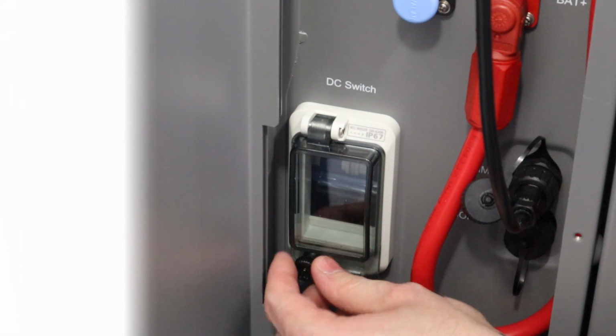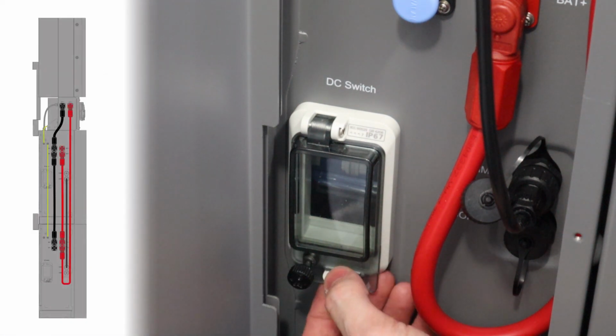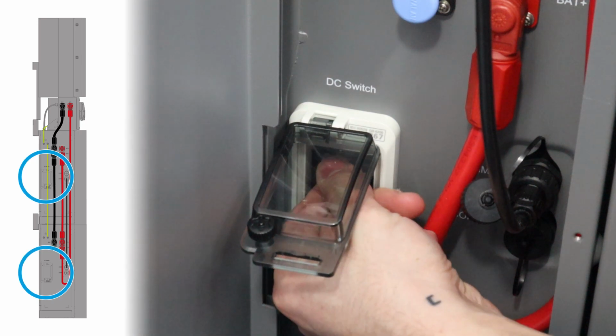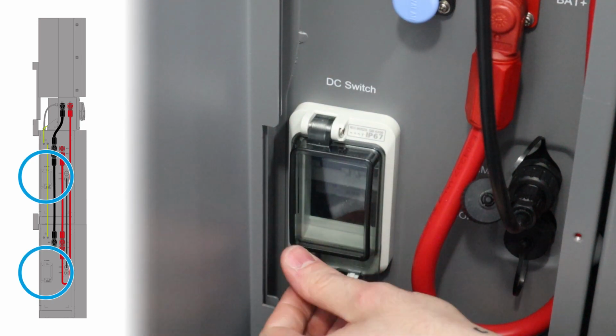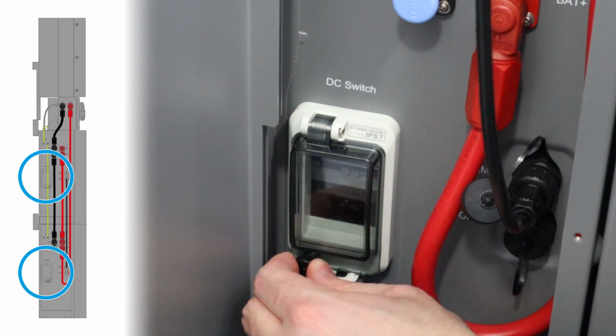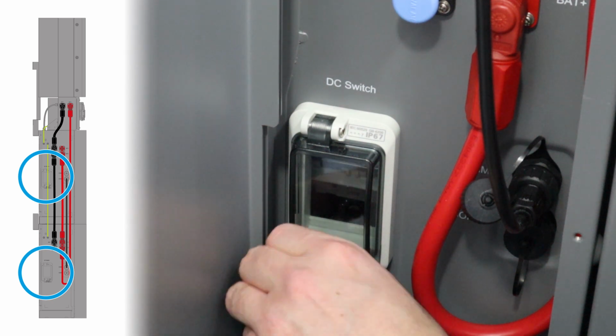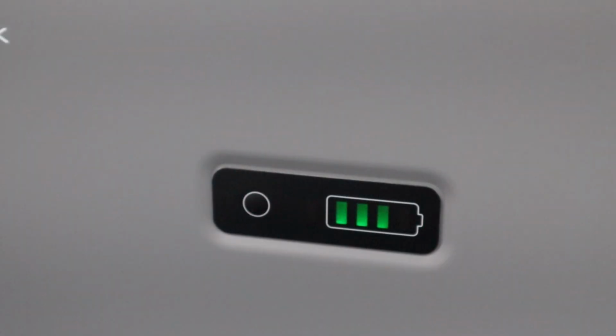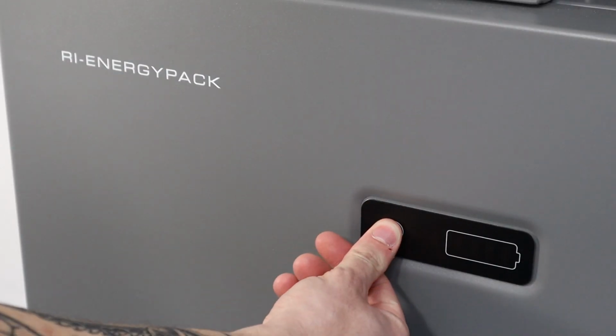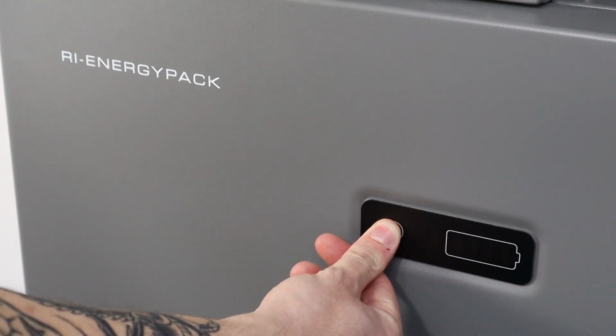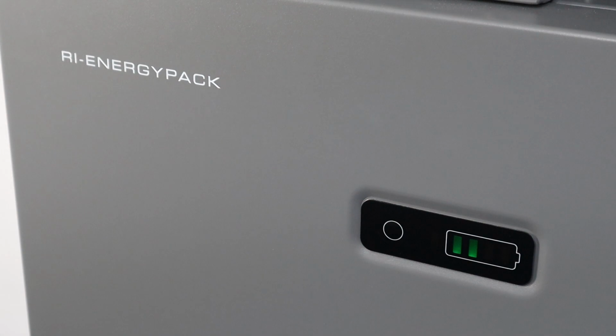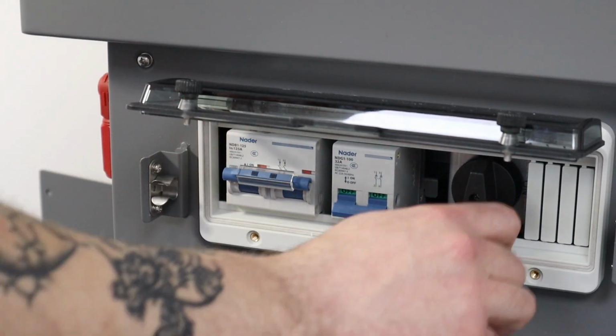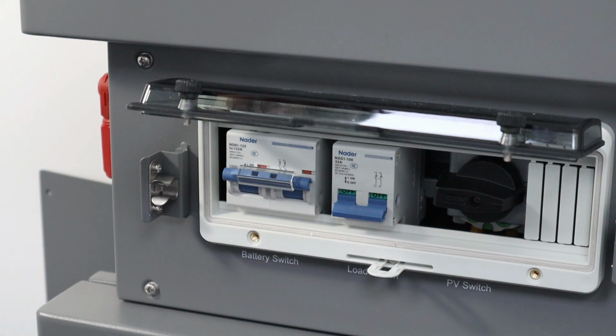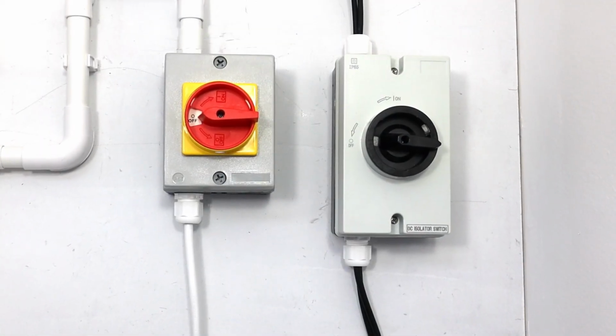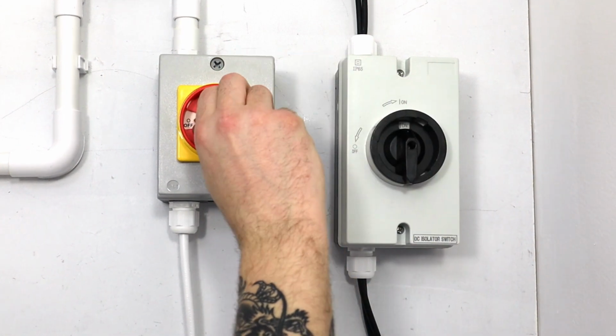Locate the DC isolator switches on each of the installed batteries and switch to the on position, then refasten the covers. The battery charge level indicators on the front of the batteries will illuminate. If it does not illuminate, press and hold the start button on the front of the battery for 3 seconds. On the front of the inverter, under the access panel, switch the battery switch and the PV switch to their on positions. Next, switch the DC isolator switch and the AC isolator switch to their on positions.